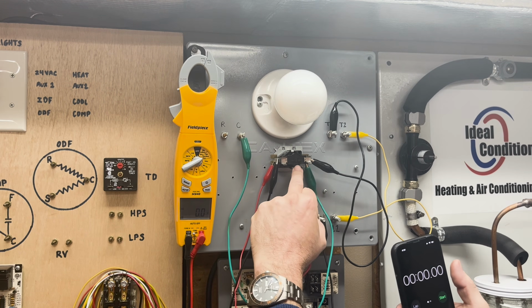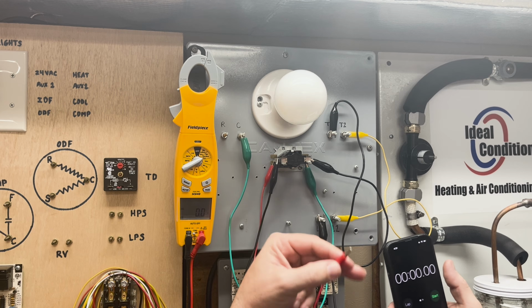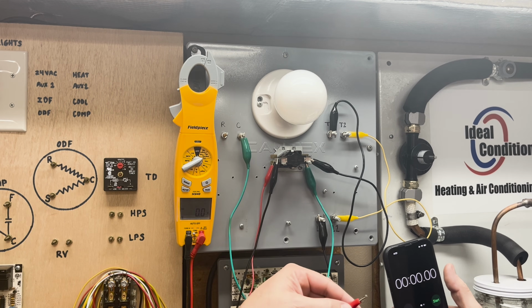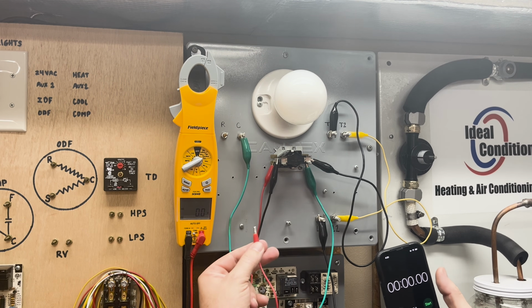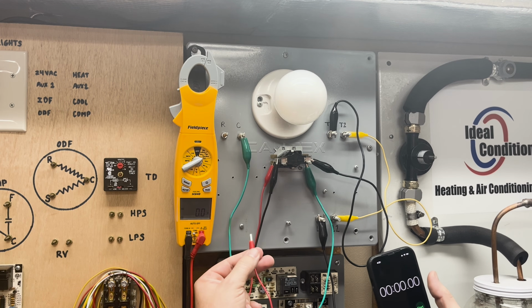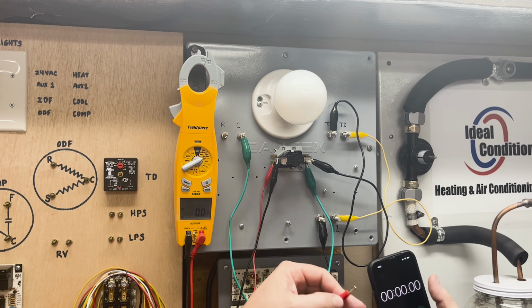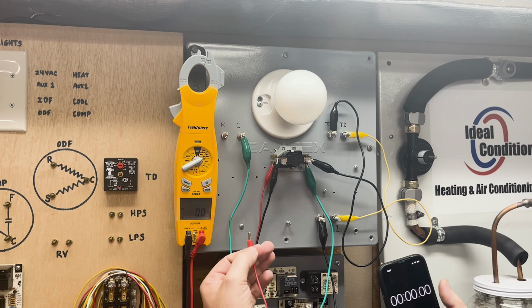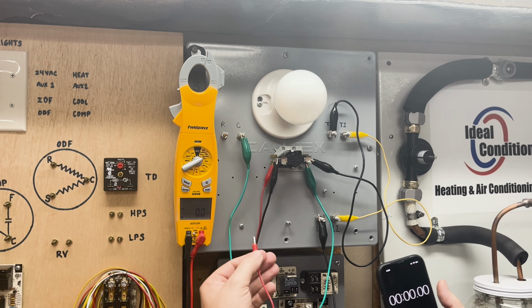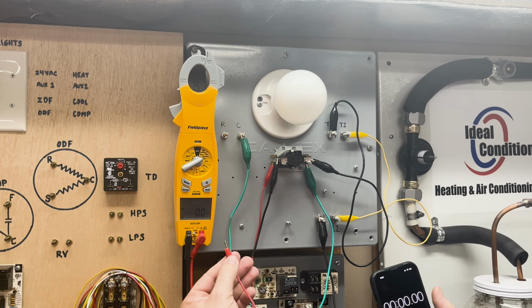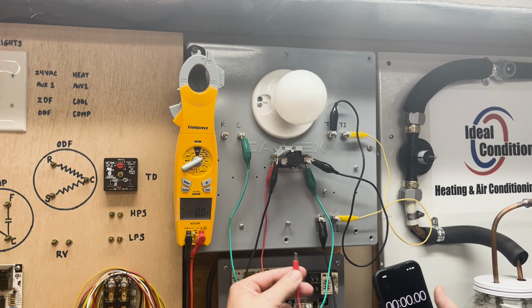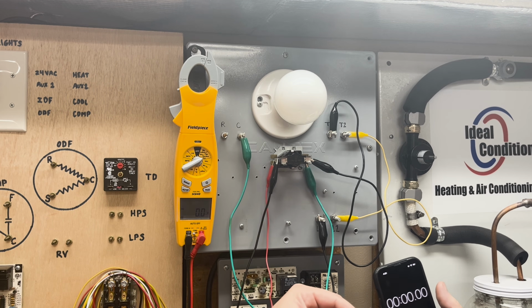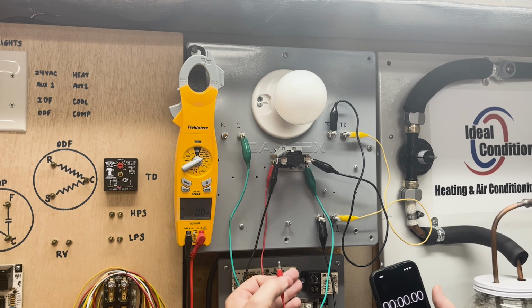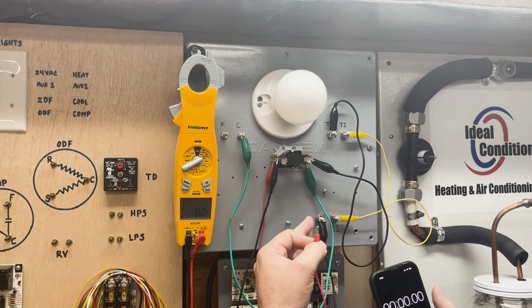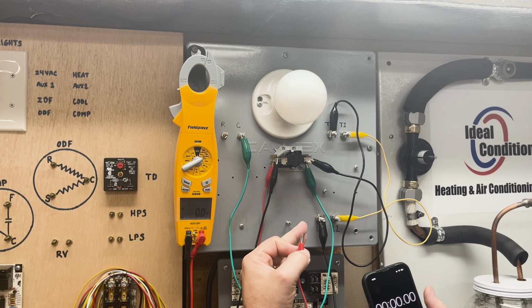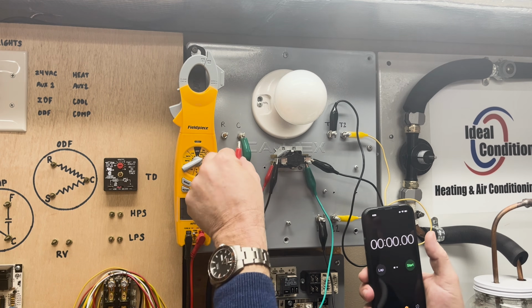Now, anytime I have a feeling that these are sticking, I always do this, because you might get one that takes 1.5 minutes to cool down. If the average is a 30 second off delay, why would it take longer than a minute? That's a fair amount of time, 45 seconds to a minute. If you're taking longer than a minute to cool down, change the relay out, because chances are it's sticking when you're not there. So we're going to try this again.